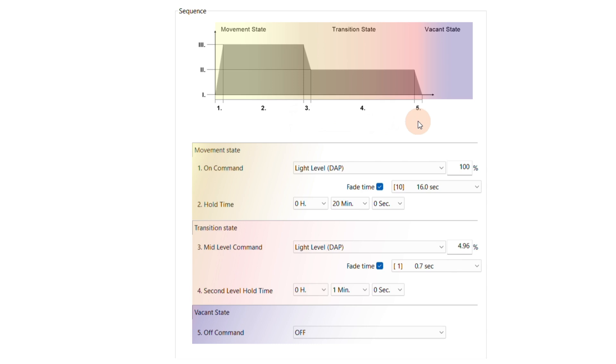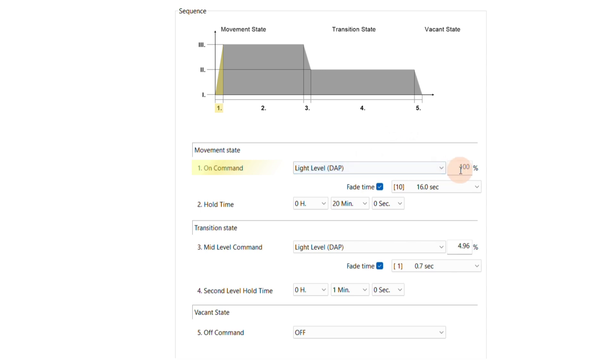Let's apply this to our installation step by step. In the section movement state, we can define an on command. This command will be triggered whenever the sensor detects movement. In our example, we choose a light level of 100%, so whenever the sensor detects movement, the lights will go to full brightness.